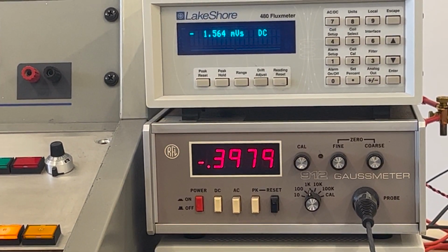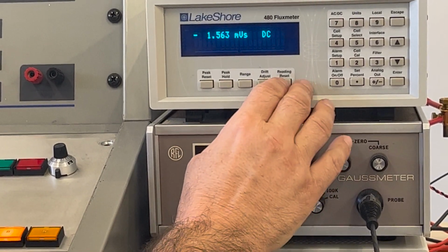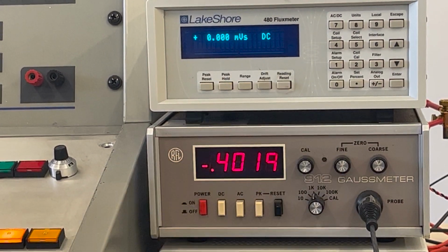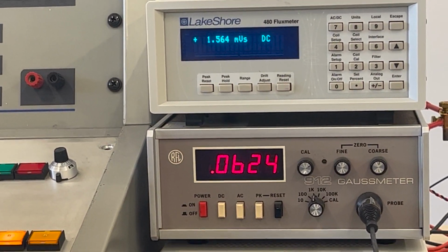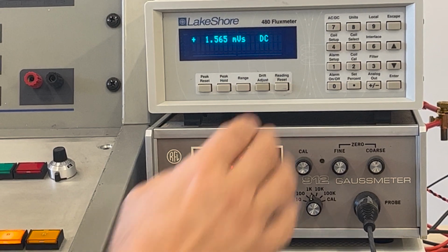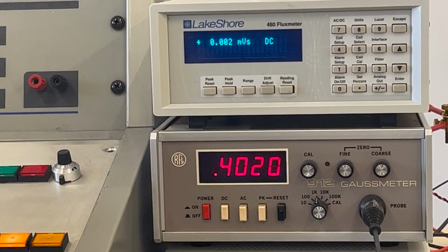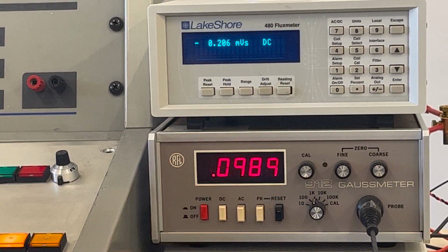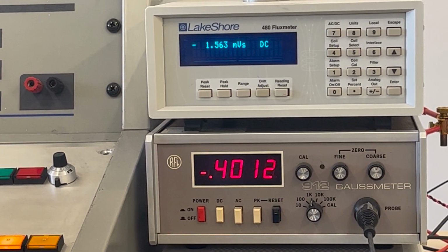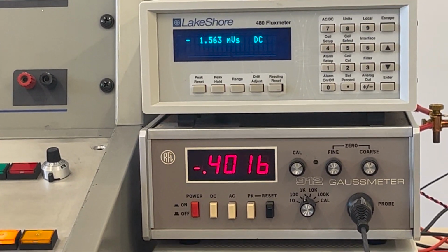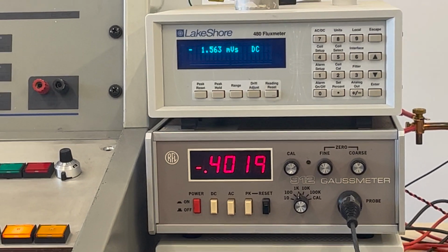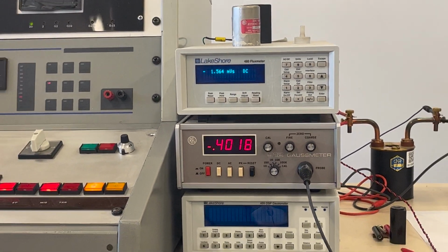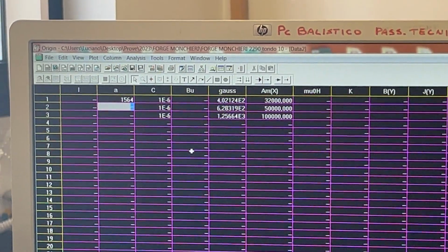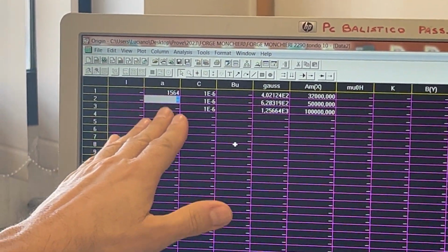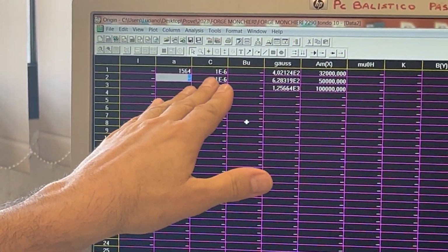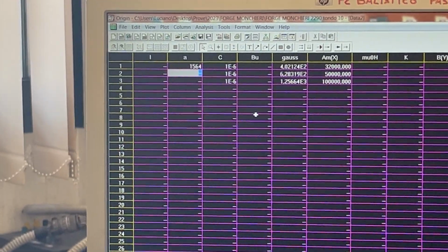Given the magnetic field that has been set in the previous step, the measurement is done by inverting its sign several times through a relay. With the flux meter, we measure the flux change associated to each reversal of the magnetic field. The flux meter is zeroed at each step. The measured flux variation at the desired field value is recorded in a table.